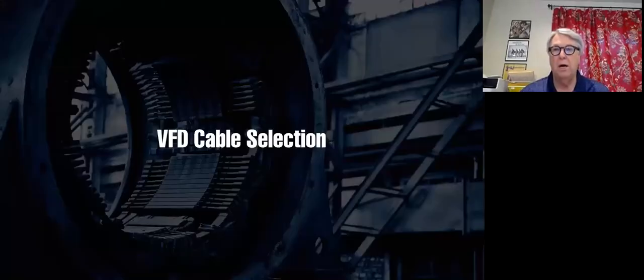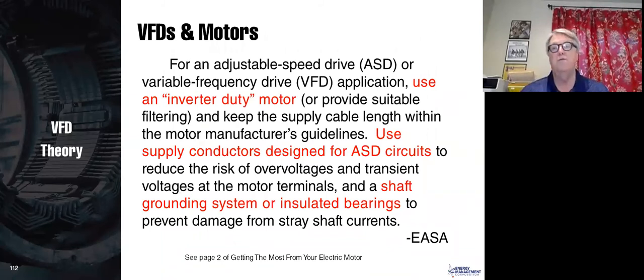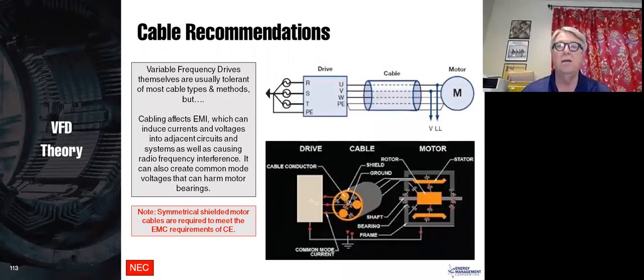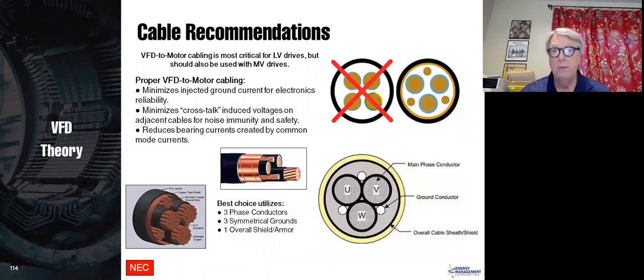Last thing I really want to talk about here is cable selection. This is from EASA, the Electrical Apparatus Service Association. They say for an adjustable speed drive, you should use an inverter duty motor. We talked about that. That has to do with the insulation. You should use supply conductors designed for ASD circuits, and you should use some form of bearing protection. So the last thing we need to look at is cable recommendations. Recently, special VFD cables from the drive to the motor have become much more popular, and most manufacturers of motors now are actually recommending that you use this. Let me show you the inside.